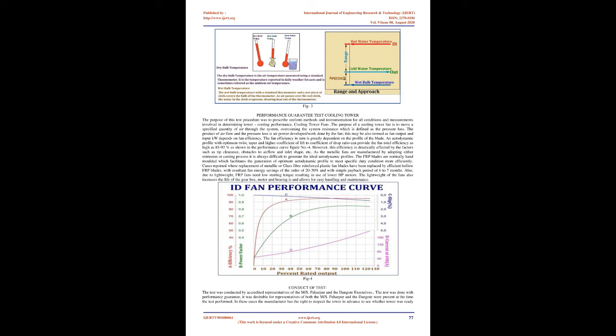At a given temperature, air is capable of coexisting with only a limited quantity of water vapor, the amount being determined by the partial vapor pressure of the water vapor in the mixture. If the pressure of the vapor in the air is lower than the atmospheric pressure, then evaporation can take place. Wet bulb temperature: the air would have to be cooled in order to reach 100% saturation with moisture.